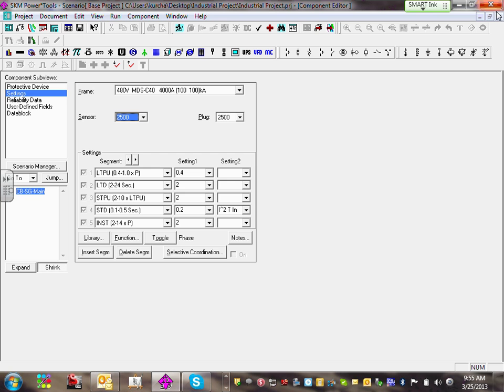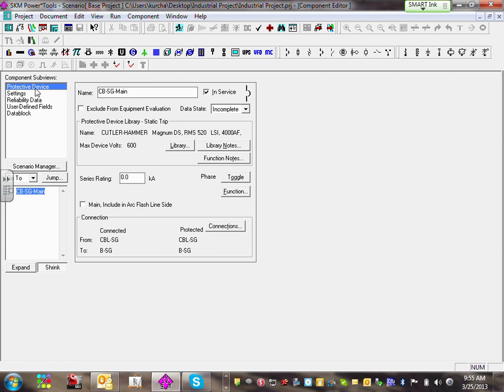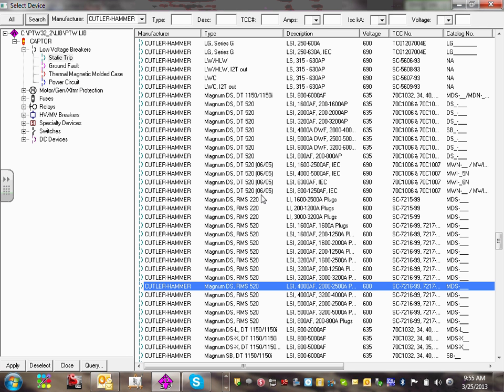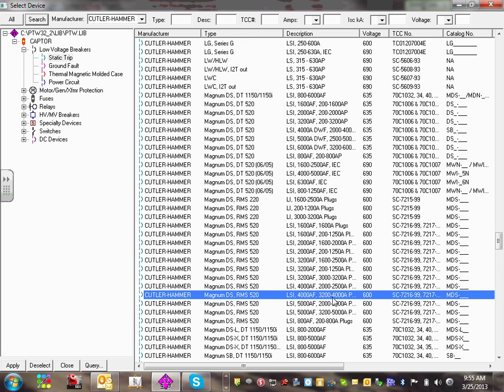Let me go back into my curves library. Why can't — oh yeah, because at 25. I want to go right here. Can you guys do me a favor for the main? Could you please go to the library and pick the one that says 32 to 4,000, because my main is 4,000 — I need a 4,000 for my main. Can you pick the one that shows long time, short time, 4,000? Double click on the 4,000. Everybody got that?